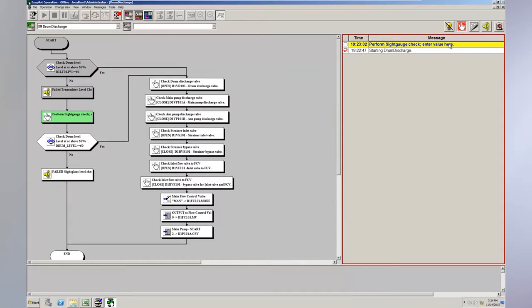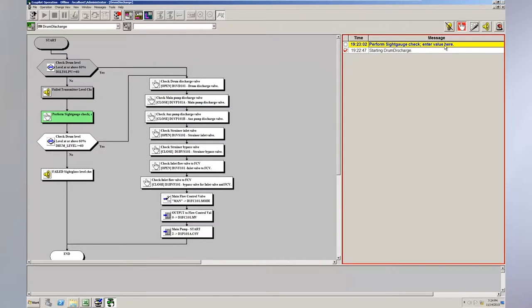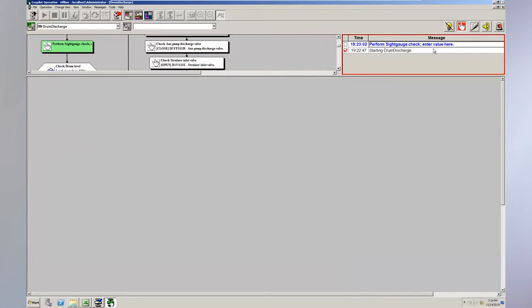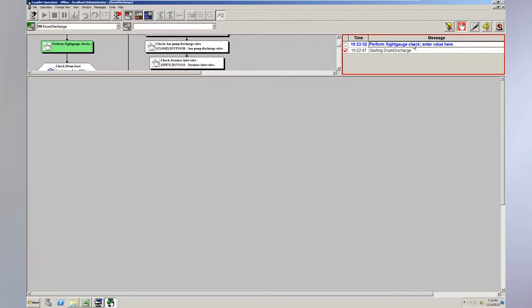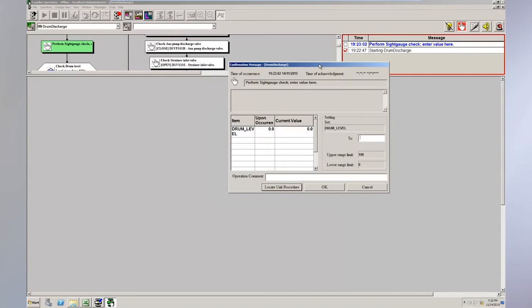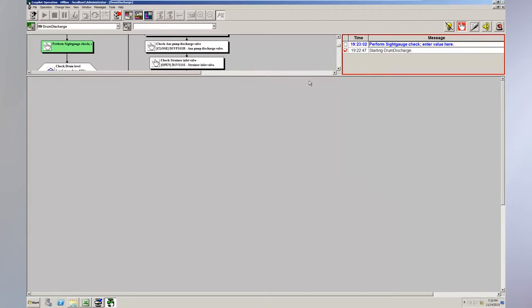We silenced that. And now we're on this perform sight gauge check. So if I select this next step, it'll bring that procedure up. And I just want to point out right now, every component you see here, the flow diagram on the left, as well as this message list on the right, either one of these components can be incorporated into an operator graphic. And typically what will happen is I would incorporate this object on the right. It's red highlighted now where it says message. It would be a really small real estate space like as shown here, about this size. We put that up on the operator graphic and you'd still see these action buttons here. And then when you were to select one of the steps that you're prompted for, you still get the pop up right on the same screen as the operator HMI, the normal DCS HMI. So the operator can still interact with that. And in this case, we'll do the sight gauge check. We'll say yes, 65% and it'll help us go on. I'm going to expand this back for this view.